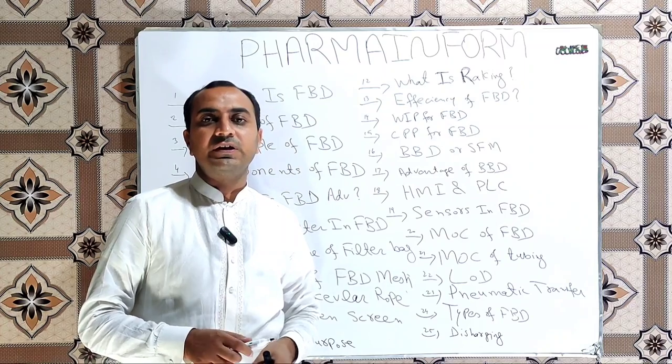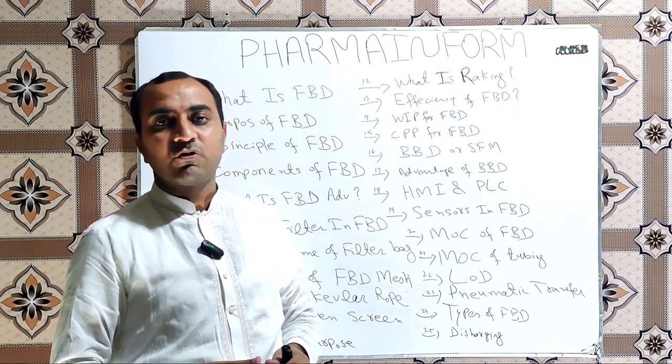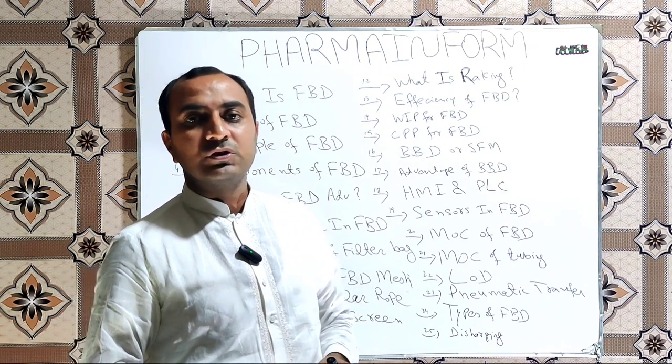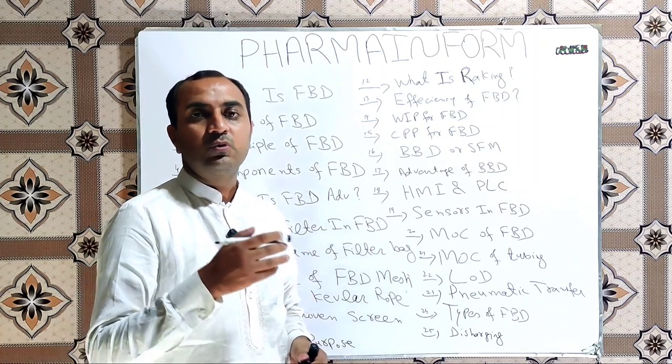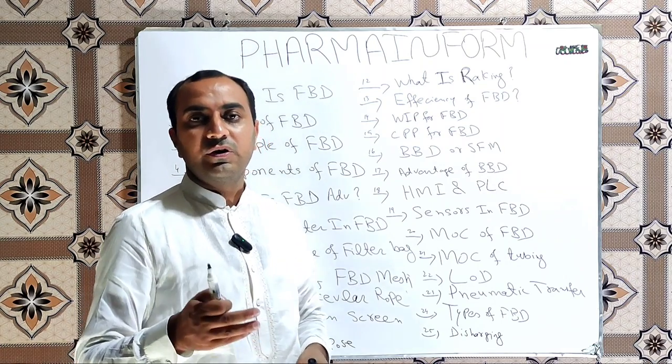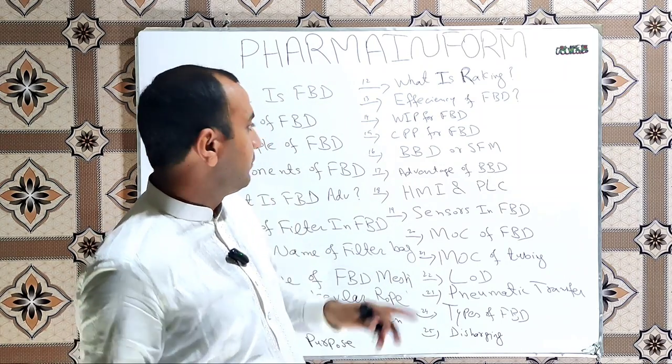What is the efficiency of FBD? As we discussed earlier, efficiency of FBD is very high. It usually takes 1 to 2 hours to dry almost 200 to 300 kg of the product.